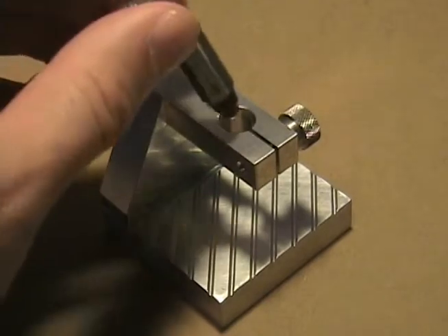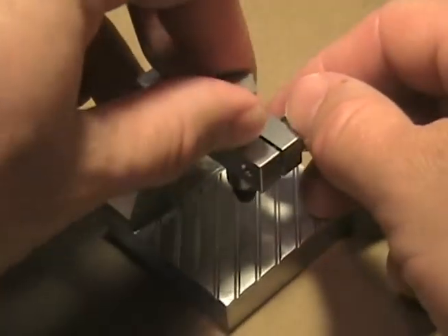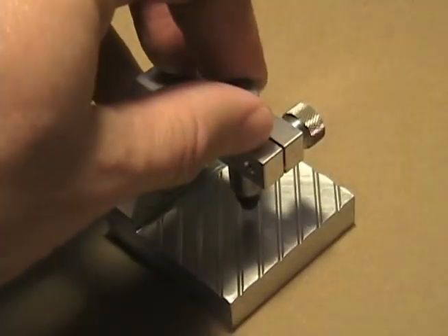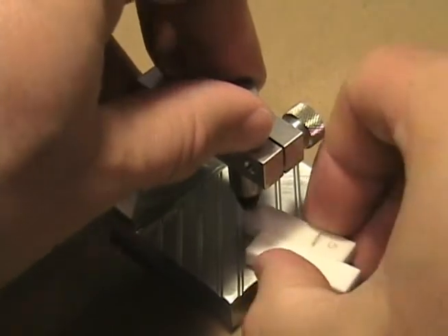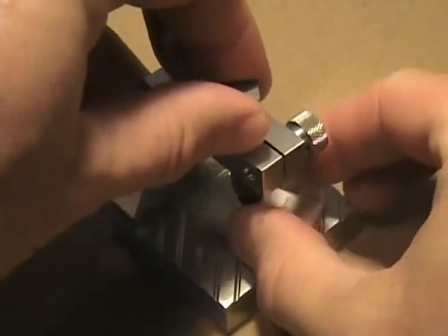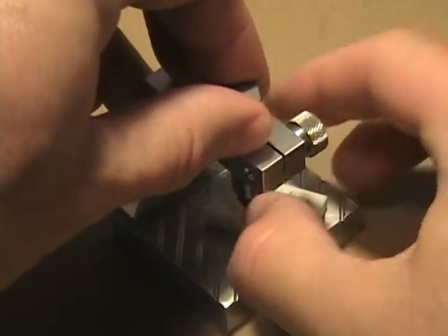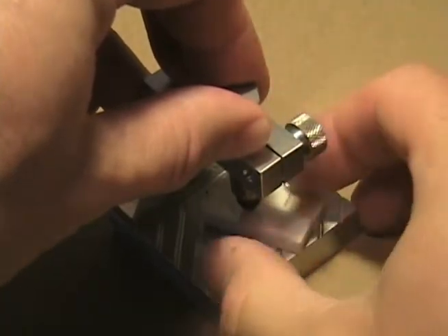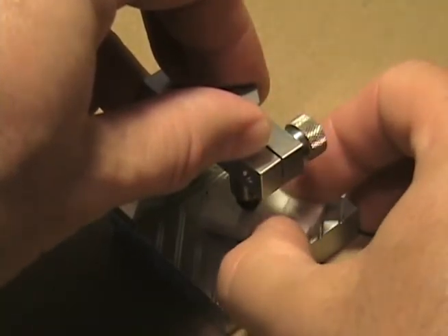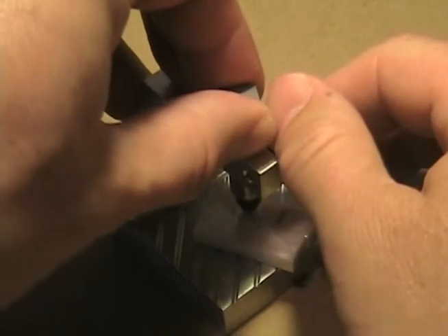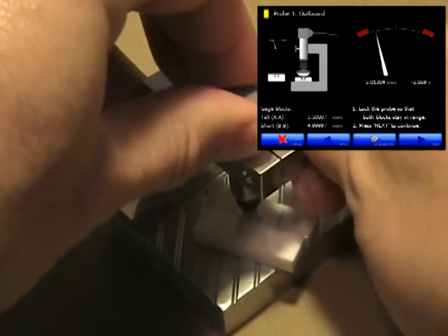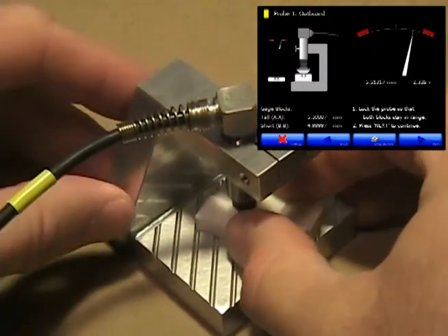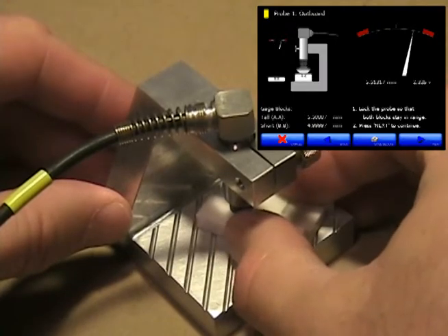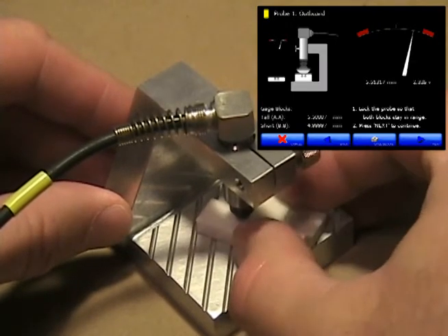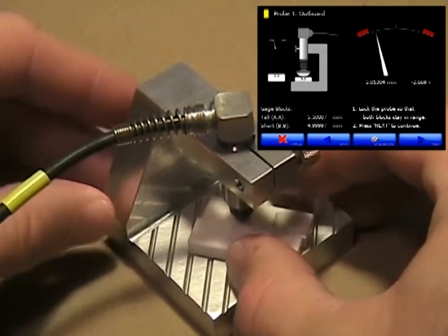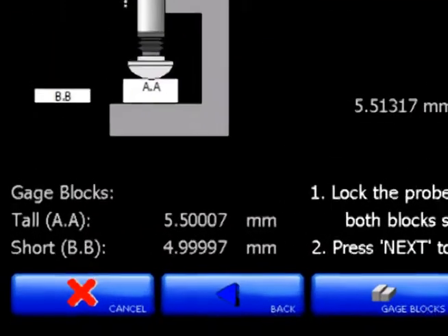So let's go ahead and mount our probe inside the calibration fixture and slide the gauge blocks back and forth under the probe and adjust the probe until the meter stays in range. Now, this is a quick process when you get used to it, but again, we're going to lock the probe in place where the two gauge blocks both remain in range on the actual meter for the probe. Once that's done, we need to take a quick final check of the gauge block values.